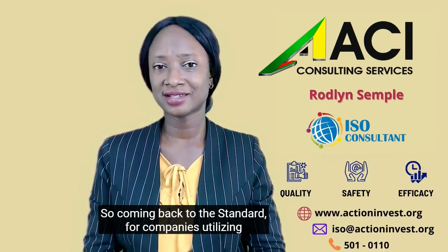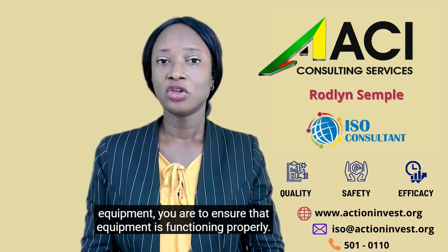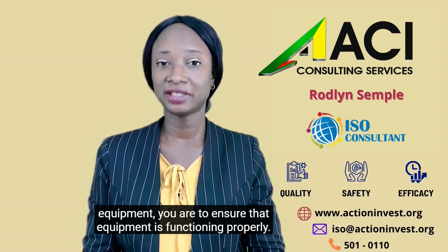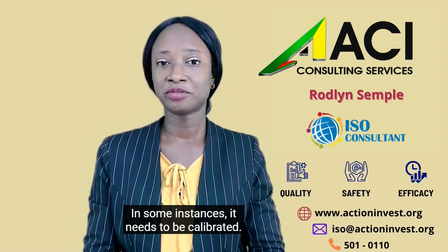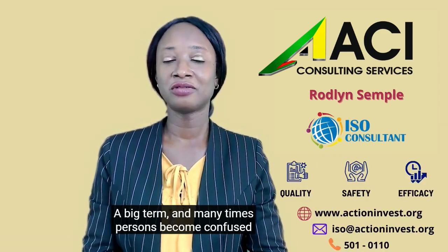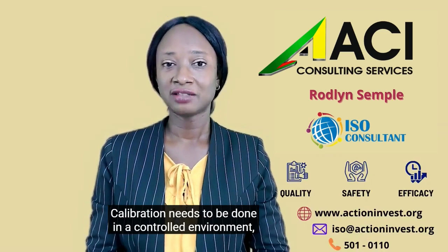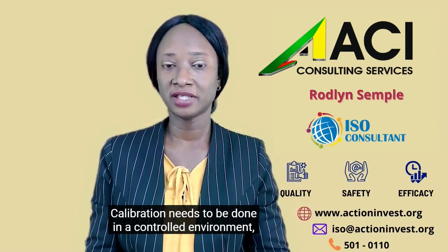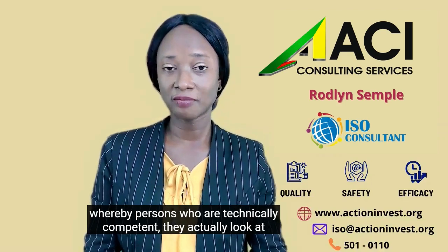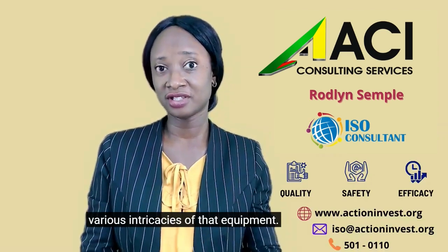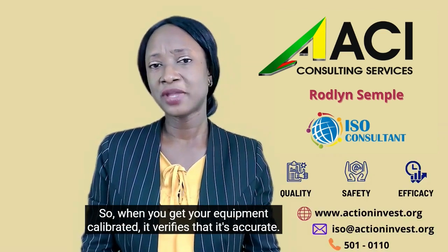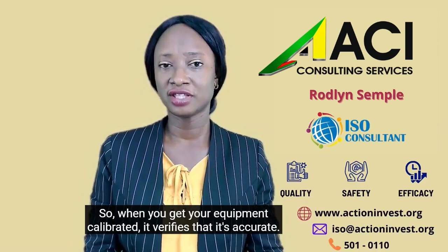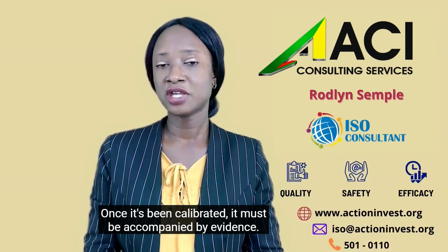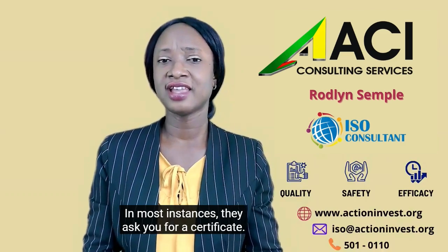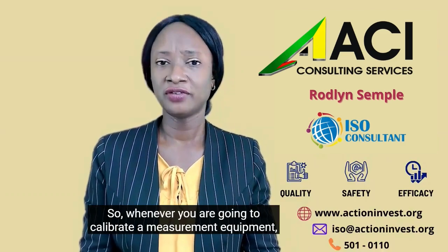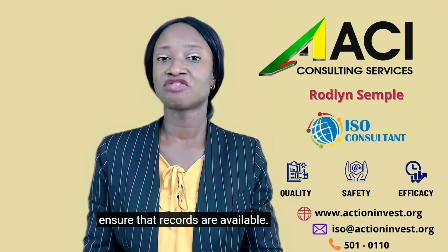So coming back to the standard, for companies who utilize equipment, you are to ensure that equipment is functioning properly. In some instances, it needs to be calibrated, a big term, and many times persons become confused with calibration and verification. Calibration needs to be done in a controlled environment, whereby persons who are technically competent actually look at various intricacies of that equipment. So when you get your equipment calibrated, it verifies that it's accurate. Once it's been calibrated, it must be accompanied by evidence. In most instances, they ask you for a certificate. So whenever you're going to calibrate measurement equipment, ensure that records are available.